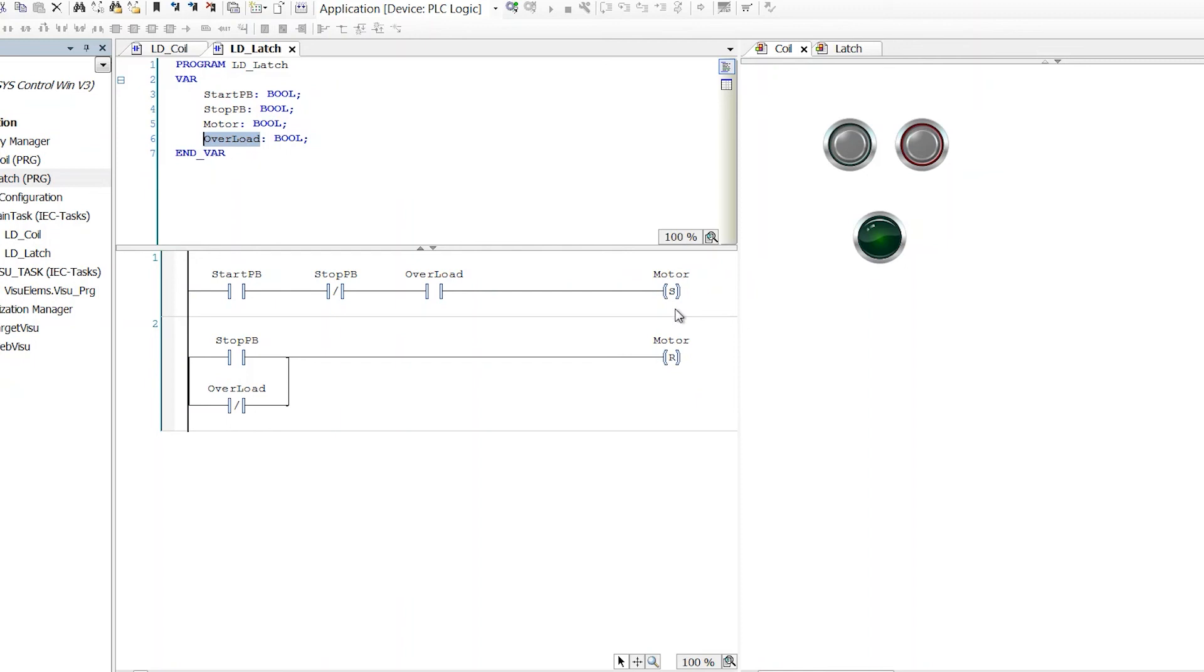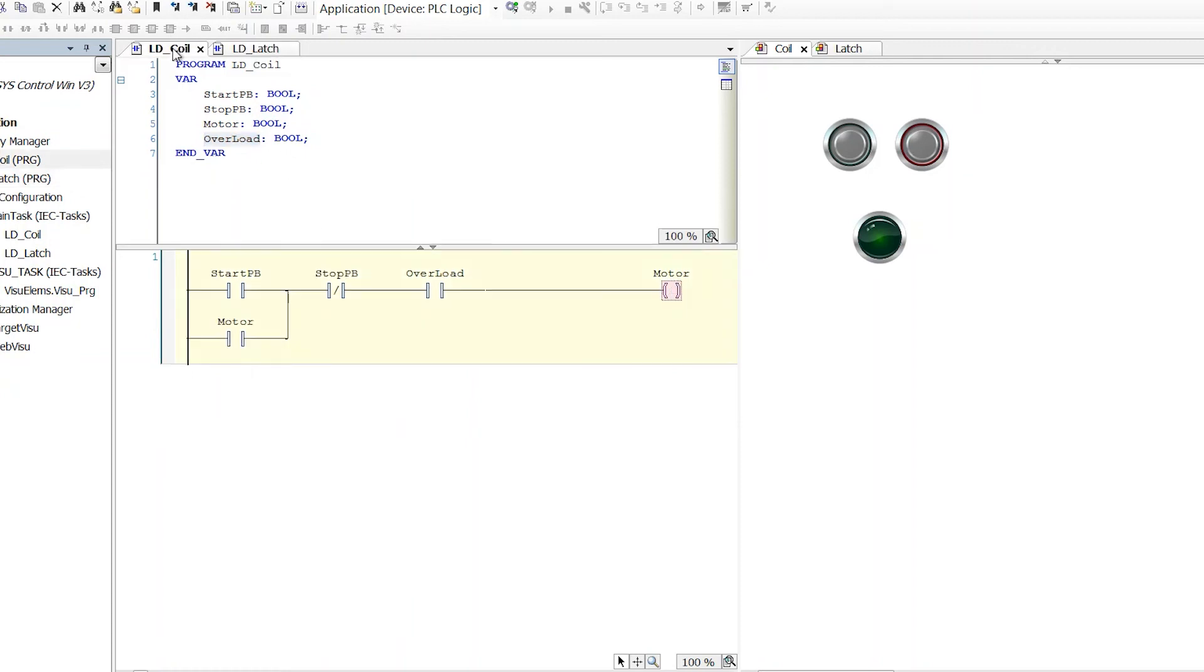But where I said some people will say don't ever use set and reset, that's probably a minority of people. Most people will say don't ever use set and reset at the same time as you're using a standard coil. So that's widely held convention. Don't do that. It's just confusing. And it doesn't make the program better.